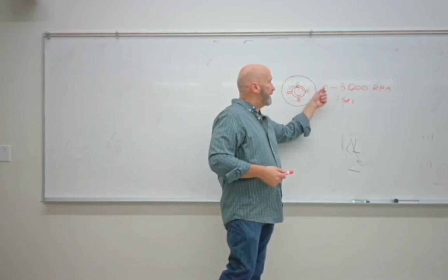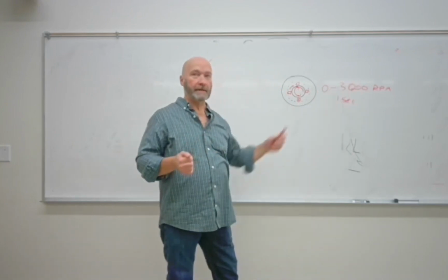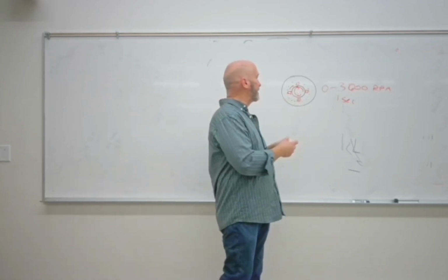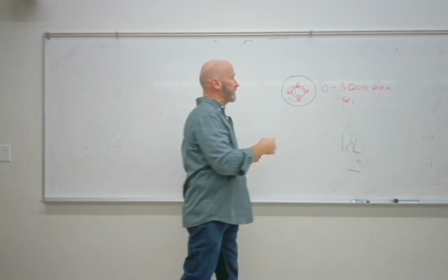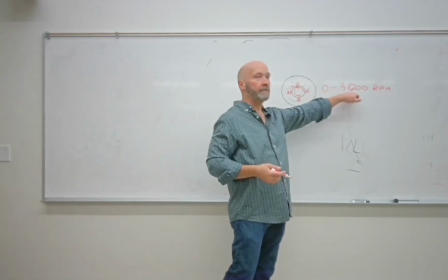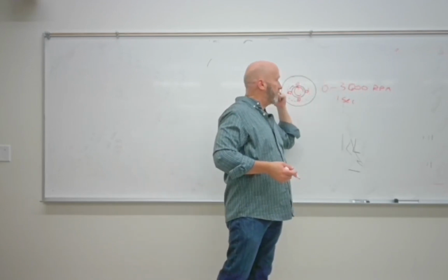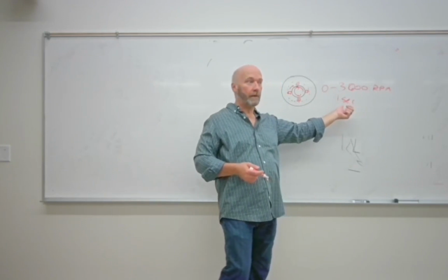We can rotate that from 0 to 3,000 RPM in 1 second. You press the prep button, and that's what happens. You start heating that filament up, but that thing starts to turn so that these things fire in a specific sequence so that you get from 0 to 3,600 RPM in 1 second. It doesn't take long. It's really, really quick.